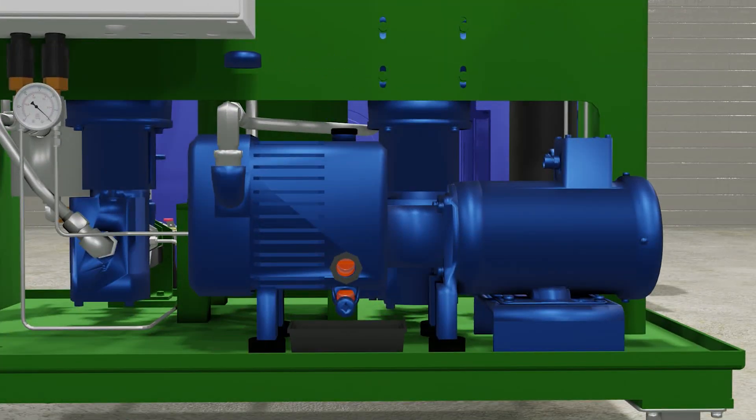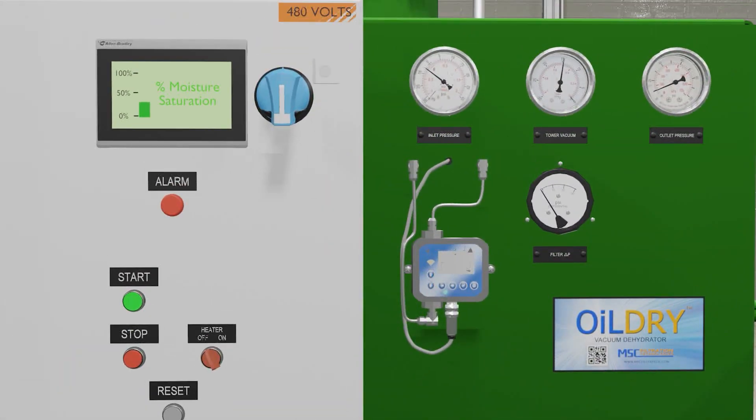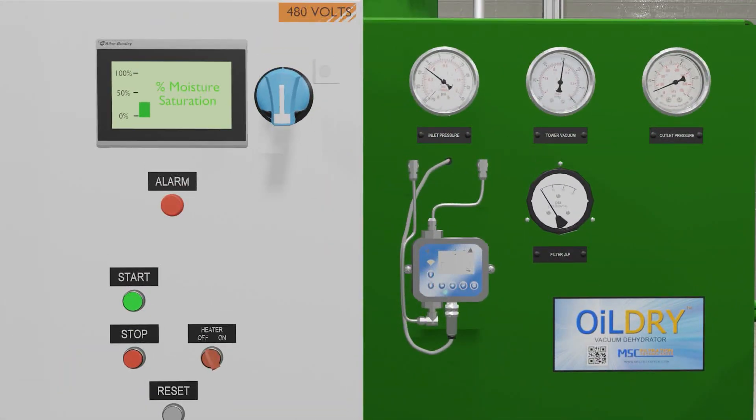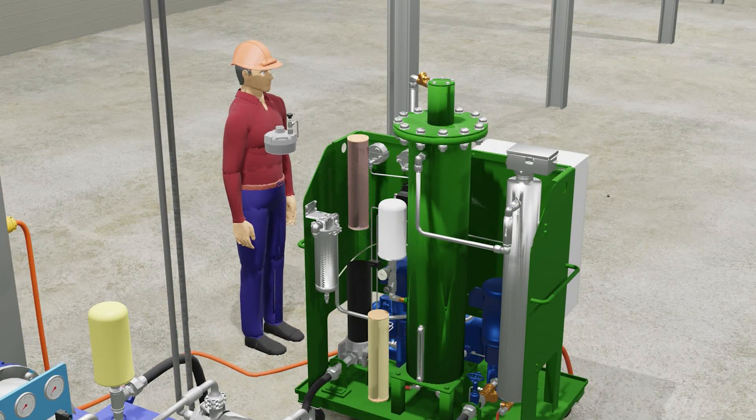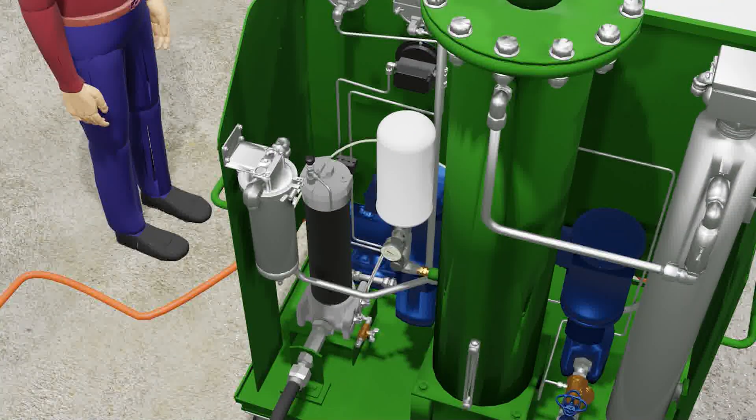Maintenance for the Oil Dry is simple. It only requires a vacuum pump gearbox oil change shown here once a year, indicated and alarmed by the Allen-Bradley PLC controller. The particulate filter change is as needed, signaled by the filter DP indicator gauge and the controller's alarm. Both tasks can be easily accomplished with an adjustable wrench and require minimal downtime.